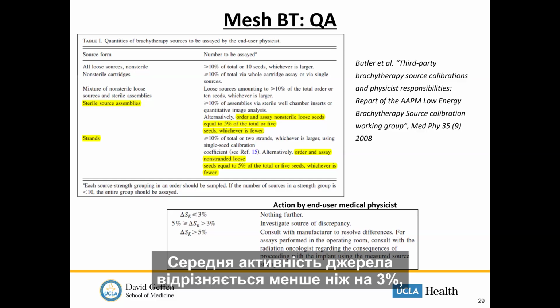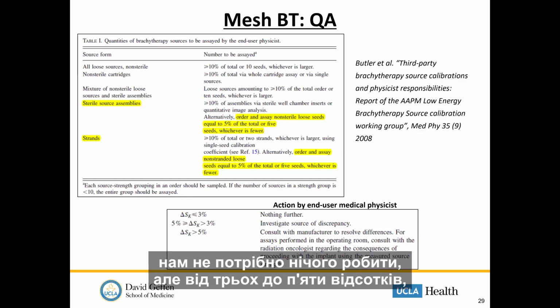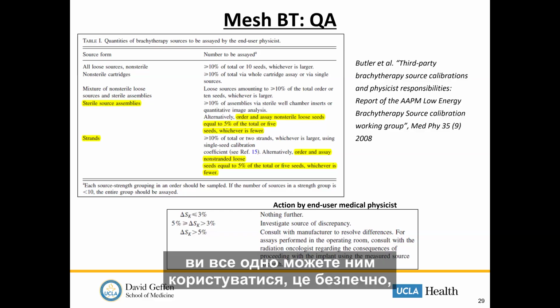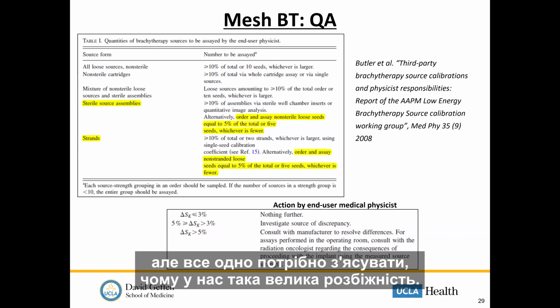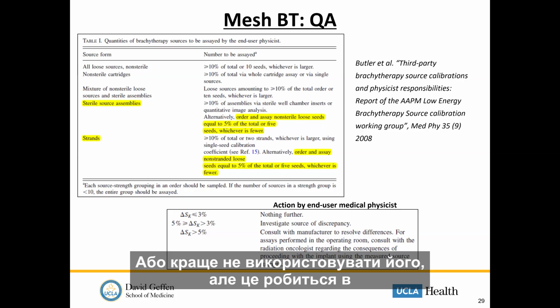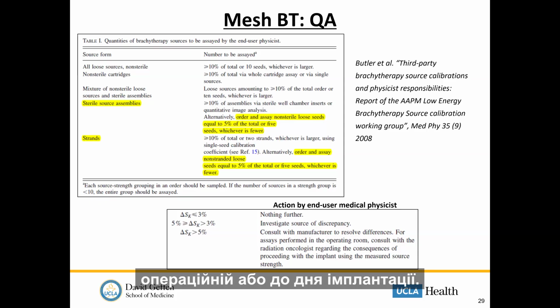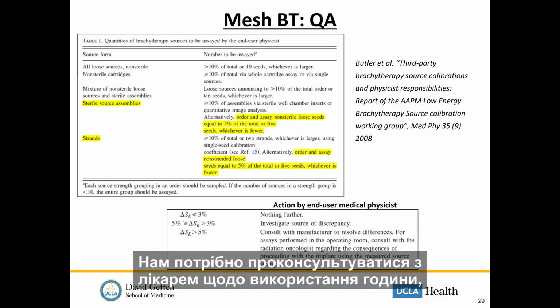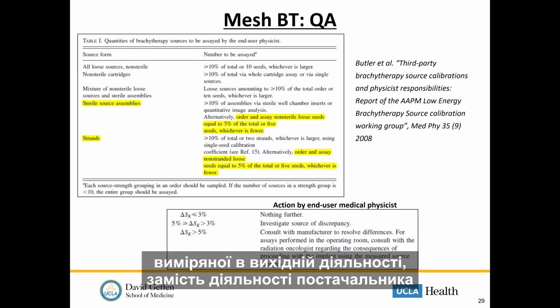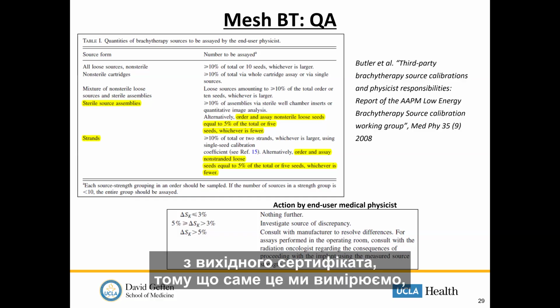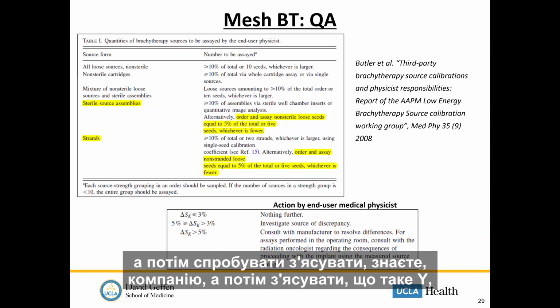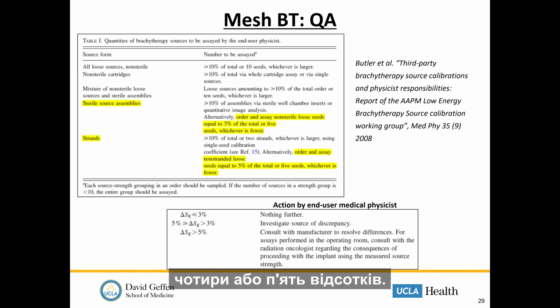If the average source activity is less than 3% different, we don't need to do anything. Between 3 to 5%, it is still safe to use, but we still need to investigate why we have this high discrepancy. At 5% or more, it is better not to use it, but this is performed in the OR or before the day of implant. You need to consult with the physician about using our measured source activity instead of the vendor activity from the source certificate, because that's what we measure, and then try to find out the discrepancy, contact the company, and find out why there is over 5% discrepancy.